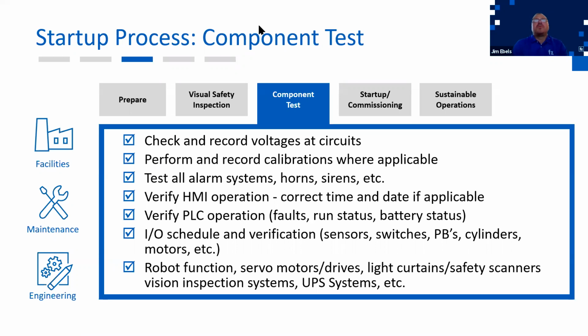Additional automation equipment you may have on your machinery and equipment that you'd like to verify operation. Robot function, checking for status lights in the home position where applicable, has proper movement, similar with the servo motors, drives, light curtains, safety scanners, make sure they're aligned again and working properly. Vision inspection systems, you want to make sure that you're checking those as well, and then UPS systems that you may have, making sure batteries are functioning properly. Next slide, please.